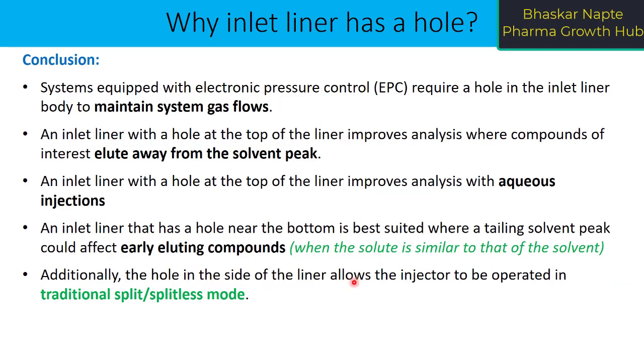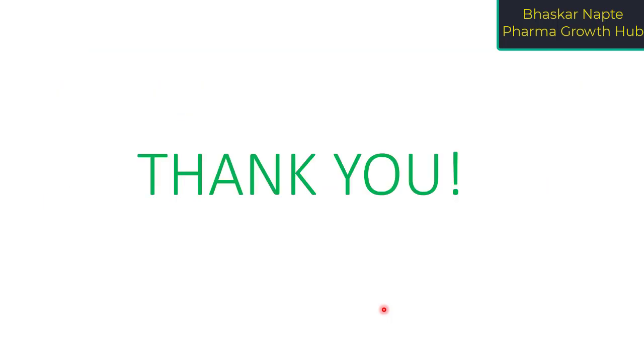Additionally, the hole in the side of the liner allows the injector to be operated in traditional split or splitless mode as well. Because this hole also helps in creating the split vent flow, it allows usage of the liner in both split and splitless modes.